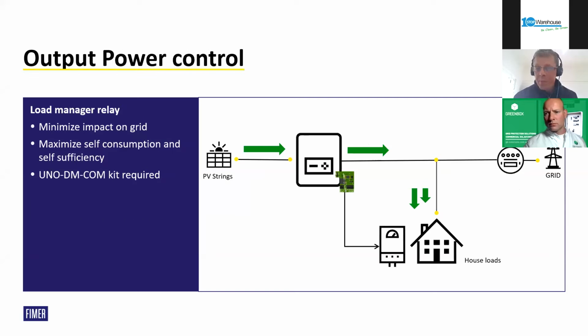Same with any output power control, so the load management relays. You will need the COM kit again to connect RS485 or any cabling to any device to switch in any sort of loads like EV chargers or pool pumps or spas or something like that. So this gives you the capability to increase self-consumption before exporting to the grid, and you can dynamically switch these loads in and off when you choose to.